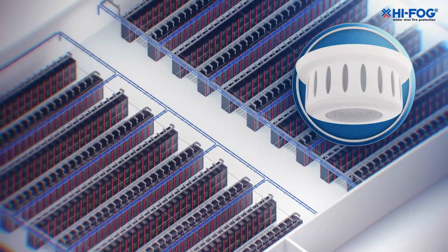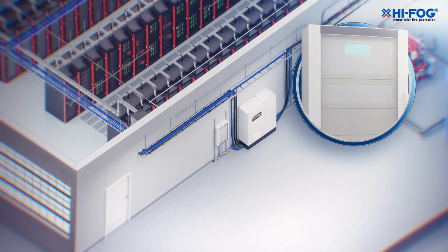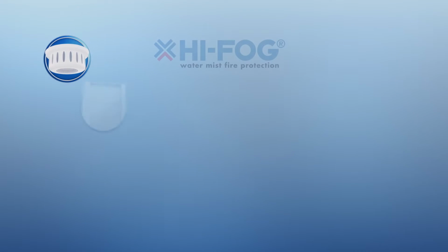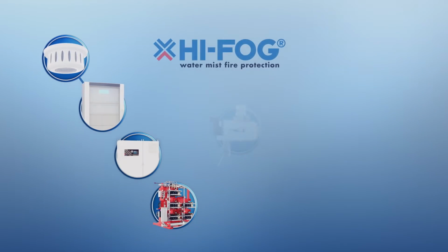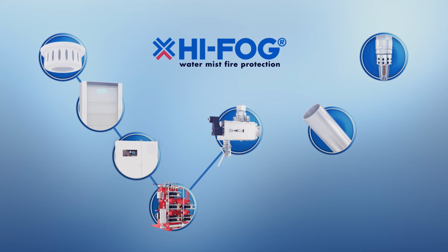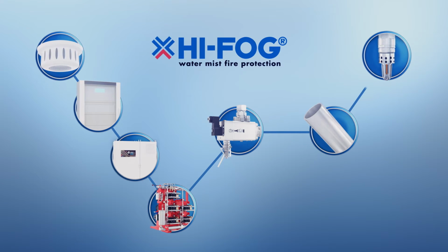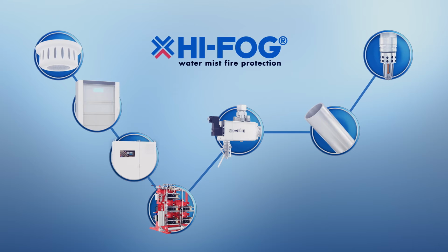Other components that the system requires are detectors and a release panel that functions as the brain for the whole system. Data center operators want to prevent false discharges in their data halls at all costs. This has been taken into consideration with the pre-action system. In case of a false alarm, the sprinklers stay closed as the bulbs are unbroken.